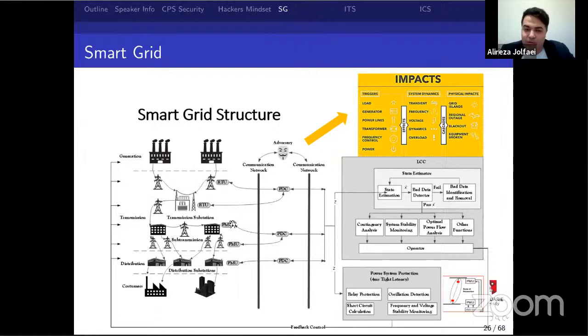For example, some of them are remote terminal units or phasor measurement units, which are more advanced, and have isolation from the high electricity. They can capture data from the high voltage line at a high frequency, the Nyquist frequency, and send this information to a phasor data concentrator that aggregates it, forming a stream of data sent to a control center.